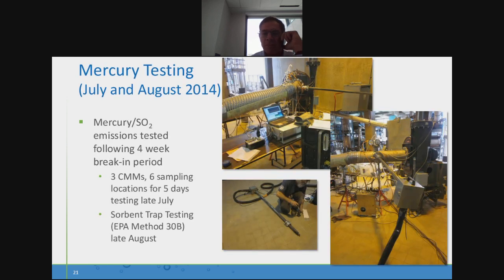So after actual 4 weeks of runtime, which again took us 7 weeks to get there with all of our ups and downs, but we did make it July and August. We performed 2 sampling events. We tested for both mercury and sulfur dioxide.